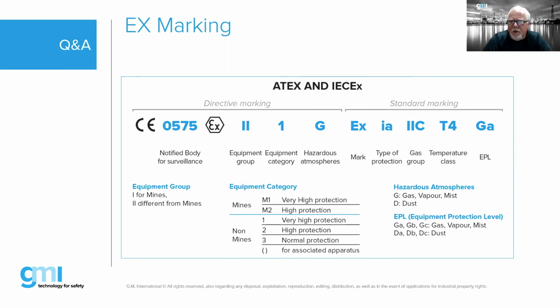Right. So every piece of electrical equipment, generally speaking, is going to have a temperature code assigned to it. And that's basically what that T code stands for: what is the relevant surface temperature of that product when it's fully energized under a potential fault condition? How hot can it get under a normal ambient condition? So any Ex piece of equipment out there, if it doesn't have the temperature or the ambient rating on it, will always be assumed at -20 to +40.